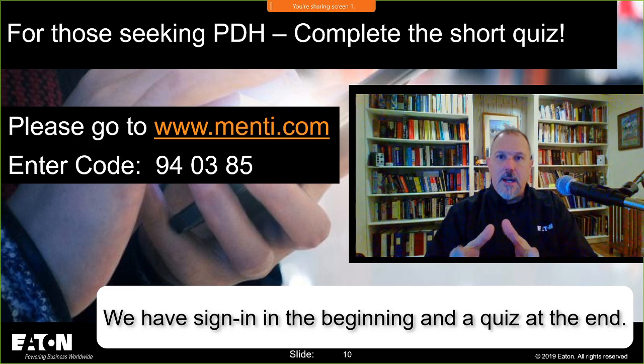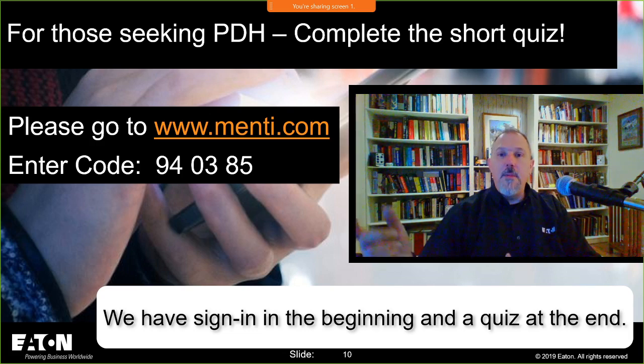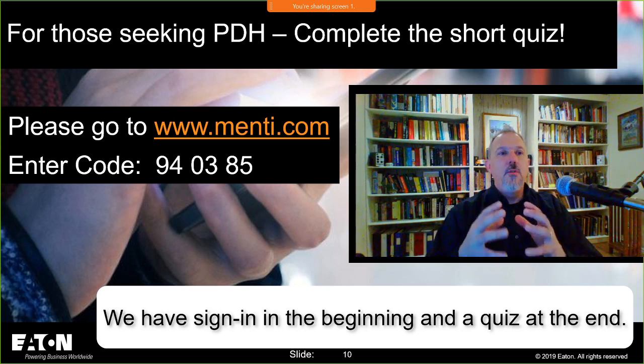So even if they did buy a dishwasher that has GFCI in the cord, it's not part of the standard to have it in the cord. So if I go out and buy another one, another brand - maybe that brand had it in the cord, maybe another brand doesn't - I buy that one, plug it in, I have no GFCI protection. So my argument is 210.8 puts it in the branch circuit. You're building a new home and you intend to put a dishwasher in - I don't care what vintage it is.